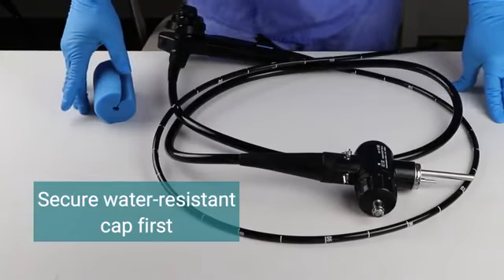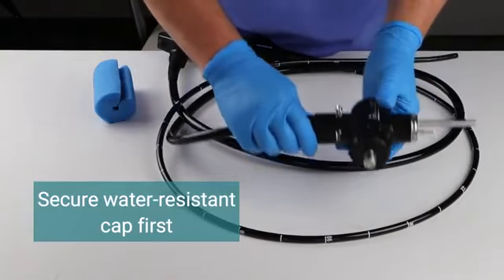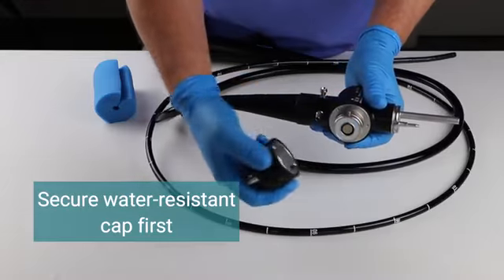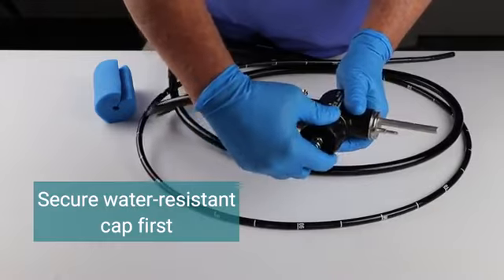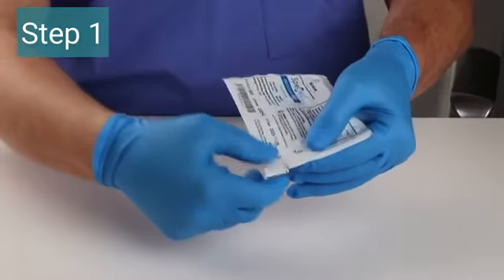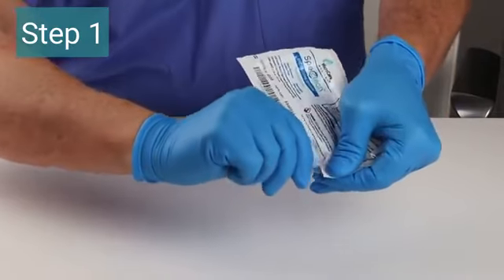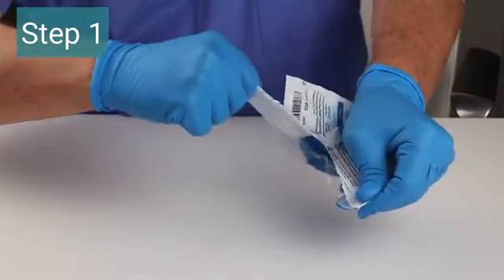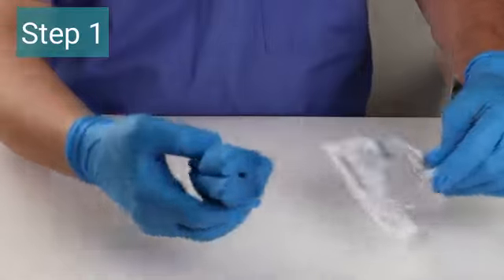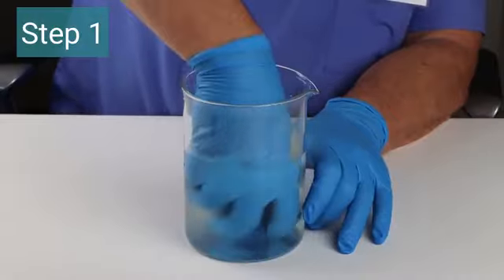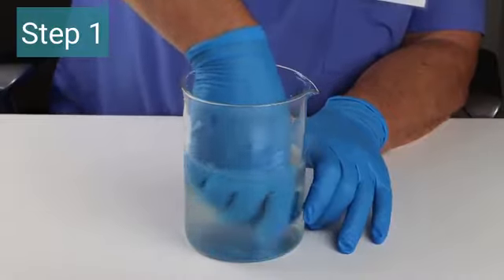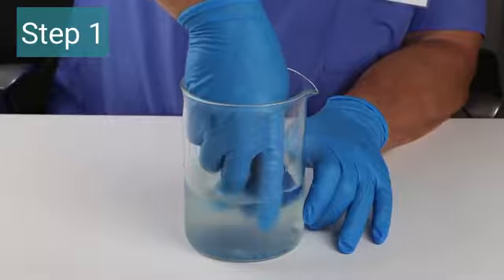Before starting, ensure the water-resistant cap on the endoscope is secure to prevent fluid from damaging the sensitive electronic parts inside. Step 1. Open the Spec Clean Endoscope Sponge packaging and remove the pre-saturated sponge. Place it in water and squeeze 3 to 5 times to activate the multi-enzymatic detergent.